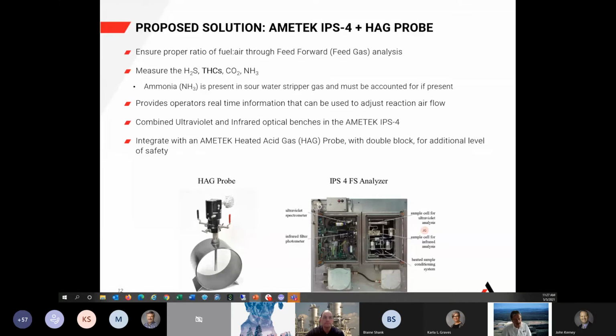I always say in my presentation, if anybody comes and tells you it's a simple H2S measurement, of course I can do total hydrocarbons. How do you want to? I use a pump. I say, okay, go away. A pump, in my view, it's not a question if it fails. It's only the question when it fails. Every pump will fail. Every pump will have a leak sooner or later. In most cases, it will have the leak sooner. What happens with a leak if you have 90+% H2S in the gas? You have 5 seconds. That's it.